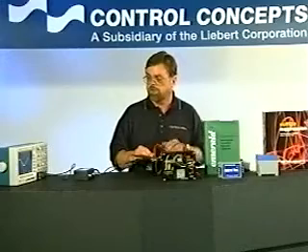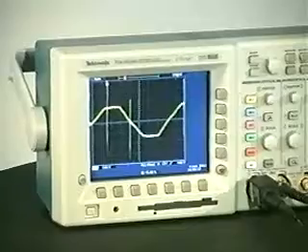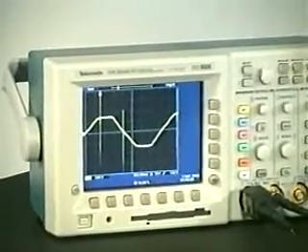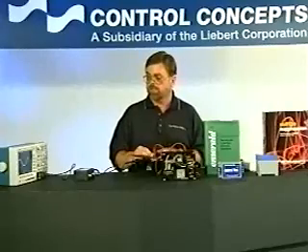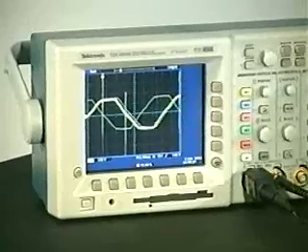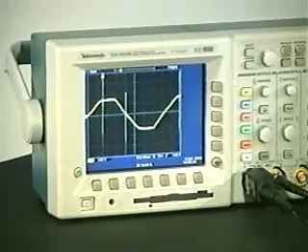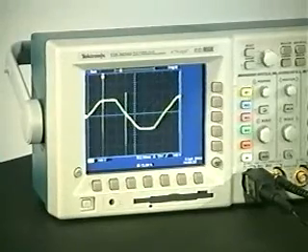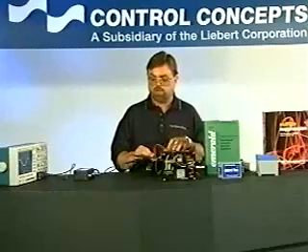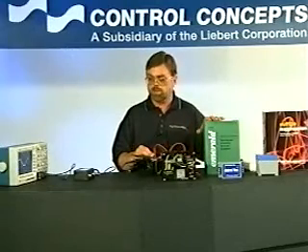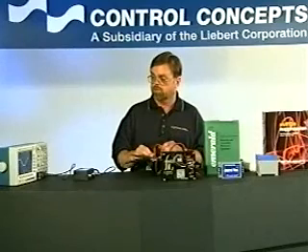To actually demonstrate that, again, I have the transients coming into the EMI filter, and this switch on the TS4 actually allows me to look at the input and the output of the filter itself. So here we're looking at the input, and when I throw this switch, there you're looking at the output. That's the input, and that's the output. You see there's virtually no difference, which is not surprising because, again, the transients generated by this generator, in reference to IEEE Emerald studies, are much lower in frequency than the EMI filter was originally intended to attenuate or reduce.